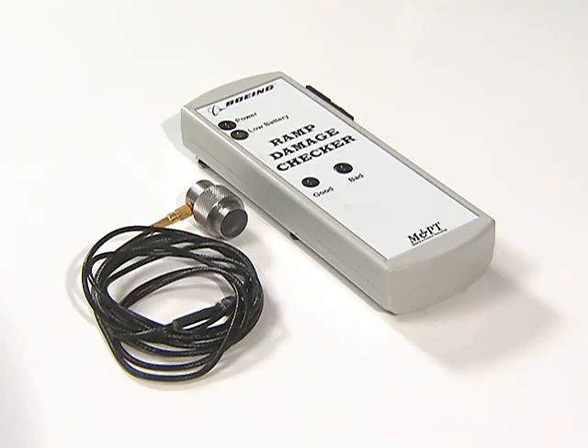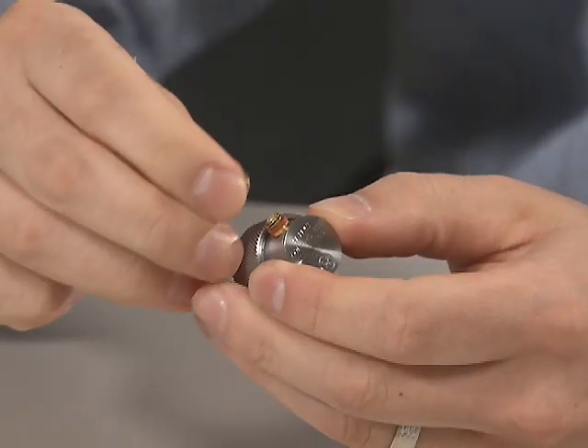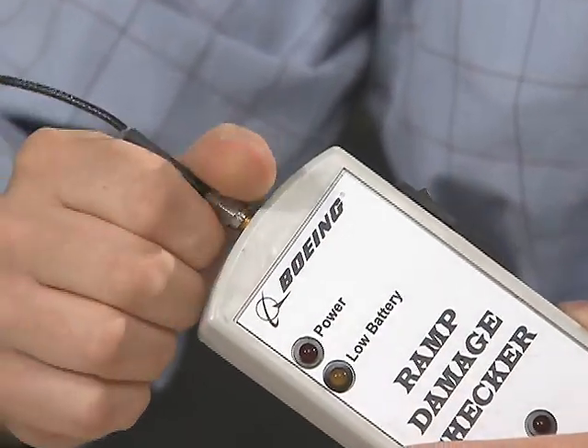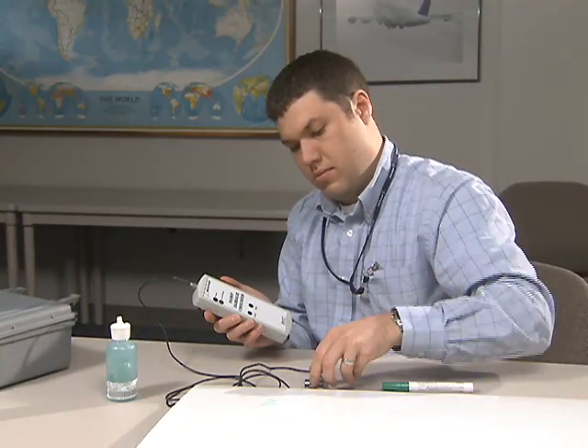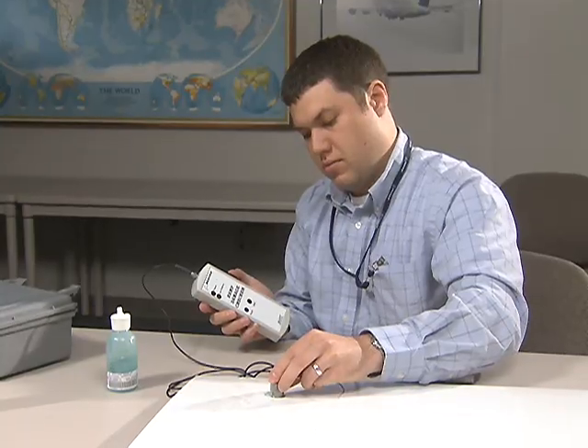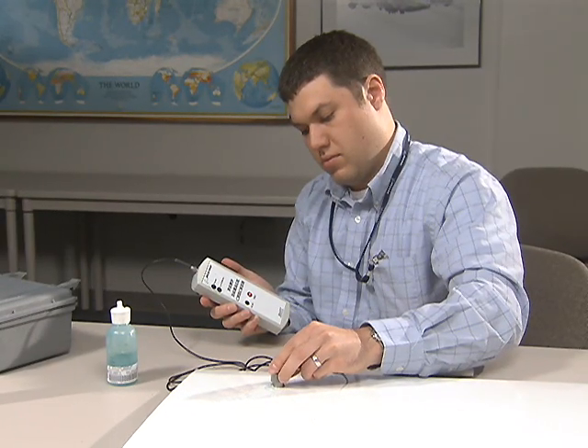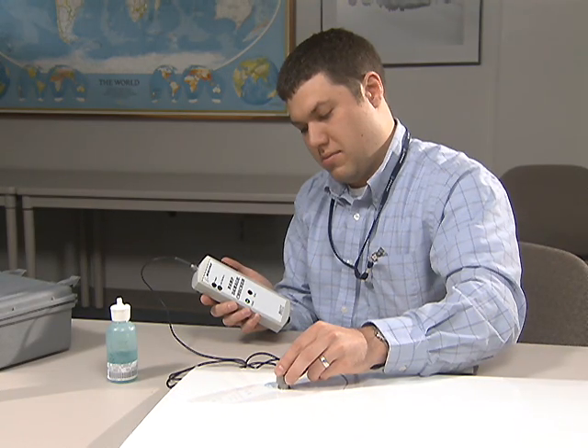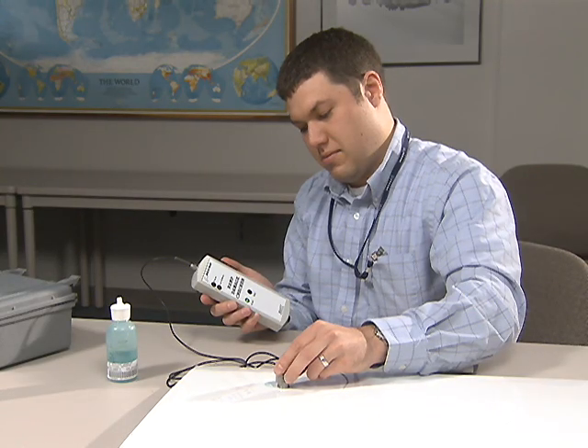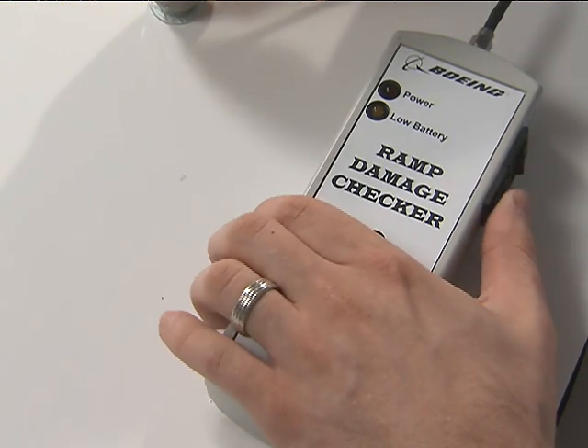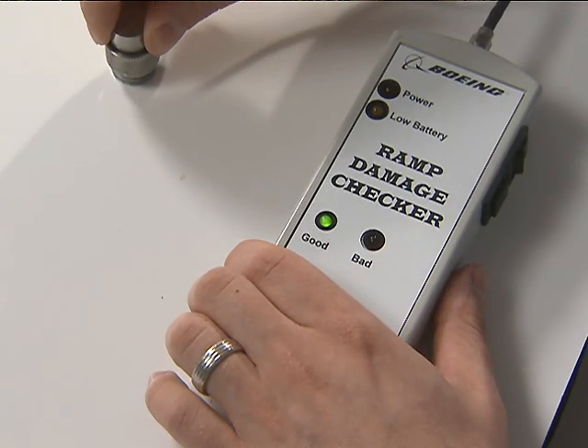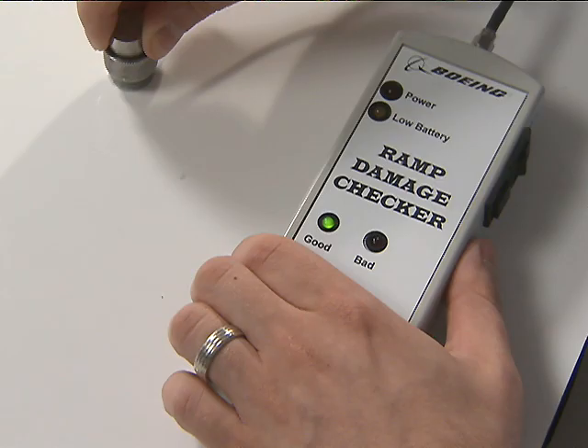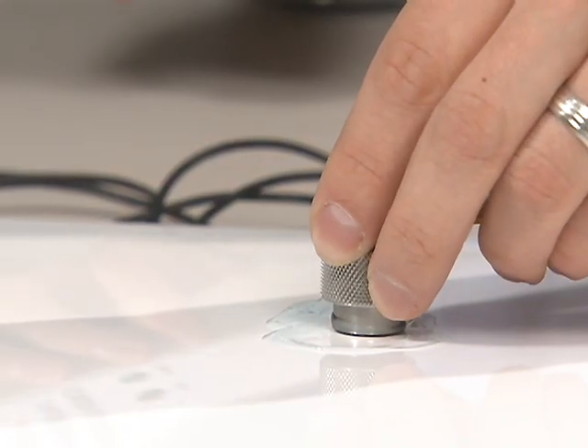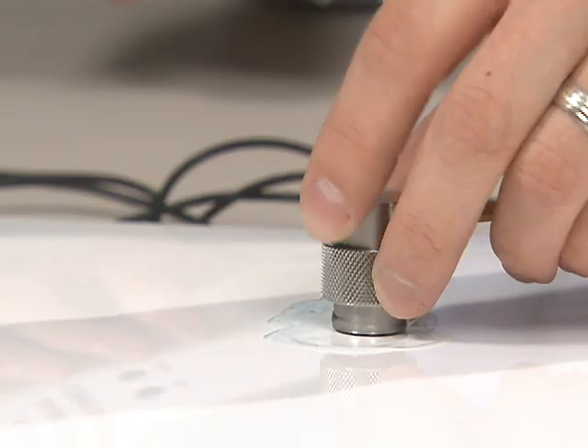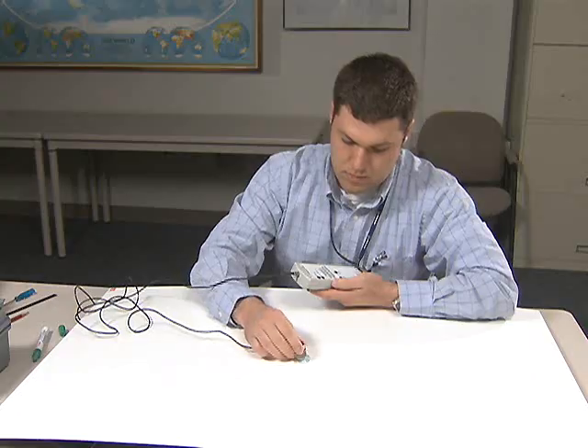The complete unit consists of the RDC, the ultrasonic probe, and a cable that attaches the two together. To calibrate the RDC, place the ultrasonic probe at least 6 inches or 150 millimeters from any visible damage and push the calibrate button. At calibration, the RDC memorizes the amount of time that the ultrasonic pulse takes to leave the probe, reflect off the back wall, and return to the probe. The indicator light will change from green to red if the unit detects an ultrasonic signal earlier in time than the signal at calibration.